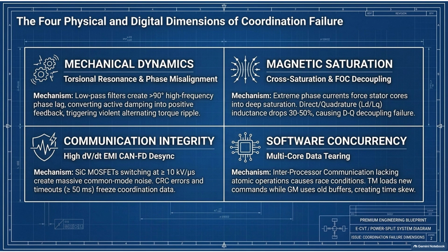And the documentation shows that the direct axis and quadrature axis inductances, the LD and LQ values, experience a sudden drop of 30 to 50%. 50%. That's a massive drop. It's huge. And that collapse in inductance is the trap, because the field-oriented control loop, the FOC, relies on a mathematical model of the motor to calculate the exact current needed for a torque request. Oh, I see. So if the FOC algorithm is operating on nominal parameters, assuming the inductances are at their normal values, it completely misunderstands the physical state of the motor. It's blind to the reality.